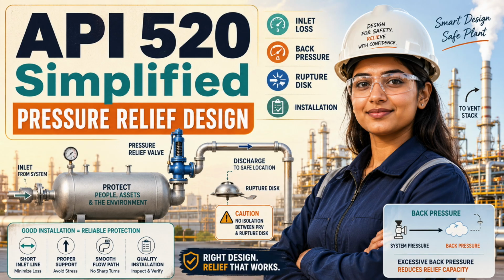Isolation valves create another human system risk. A perfectly sized relief device behind a closed isolation valve provides no protection. Where isolation is required for maintenance, testing, or online switching, the arrangement must ensure that adequate relief capacity always remains available. That may require locked or sealed open valves, interlocks, transfer arrangements, position monitoring, controlled procedures, or full spare relieving capacity. Two valves do not automatically create redundancy.